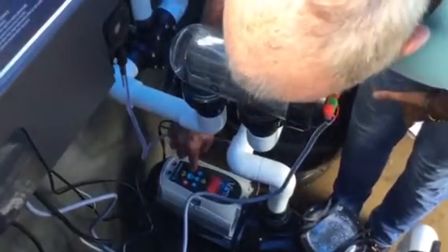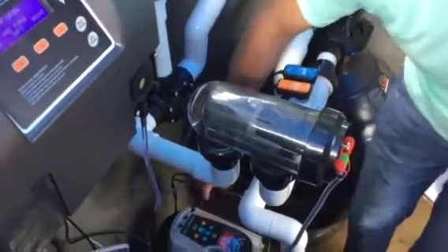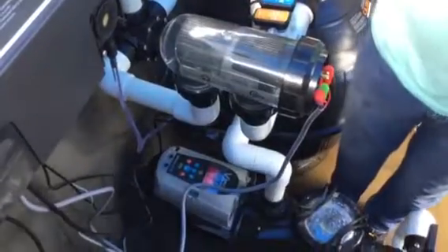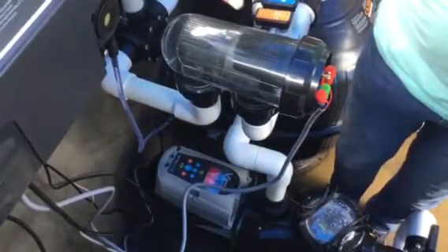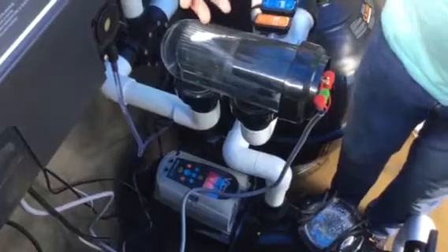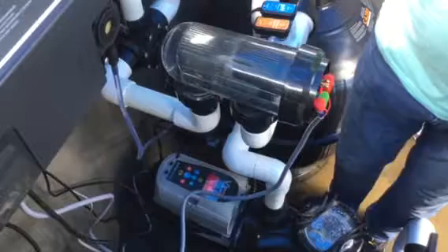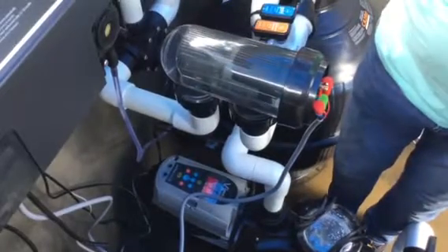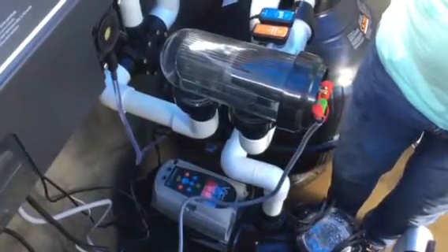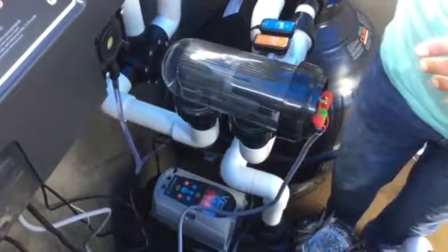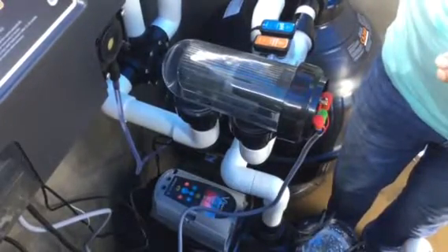So you can manually override what your default pump speeds are. The reason why we did that is because you quite like 2000 as your default speed. So when all things are set up normally in AI mode, this will run things at default. It'll run the pump at low, and we've changed the low speed to be 2000. So when all things are balanced, this will just run at 2000, instead of 1325 as factory default.